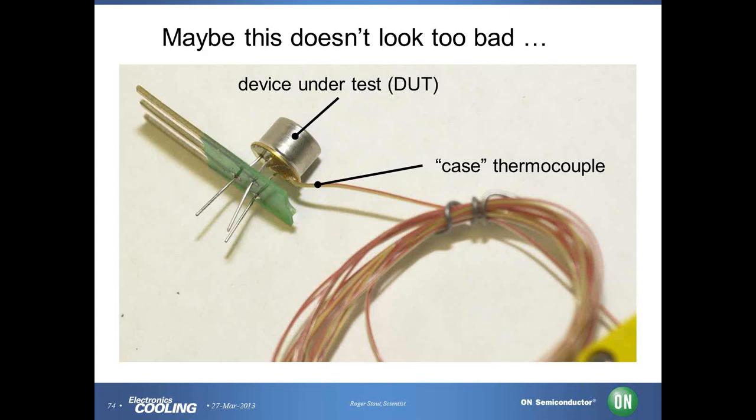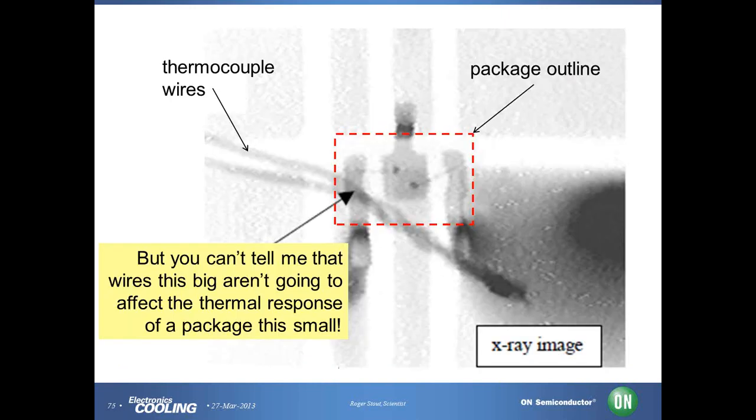Thermal characterization itself also brings me up against some persistently frustrating issues. Take thermocouples, very simple temperature measuring devices we use all over the place. The most obvious problem, I think, is that when the thermocouple itself is as large as the device you're trying to measure, you're going to cool it significantly. T-type thermocouples, for instance, are particularly bad this way because one of the two wires is copper. Others, K for instance, are much better in this regard because both wires are relatively poor thermal conductors.